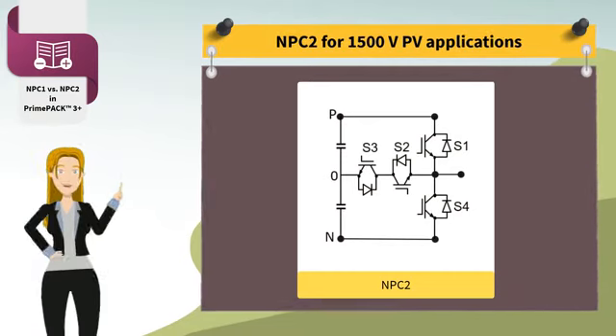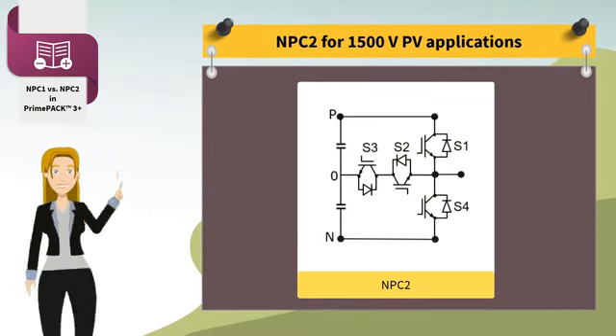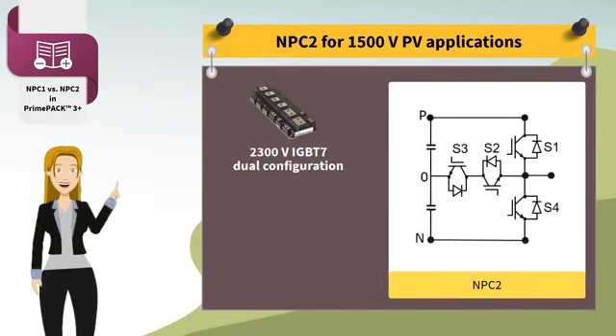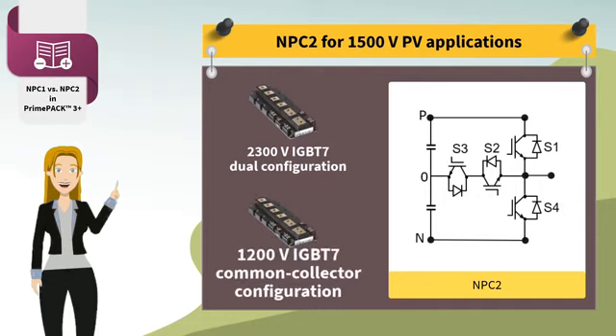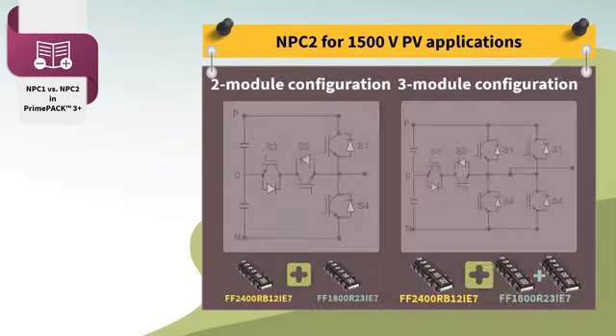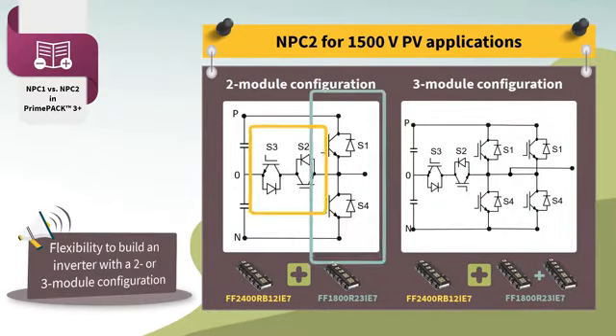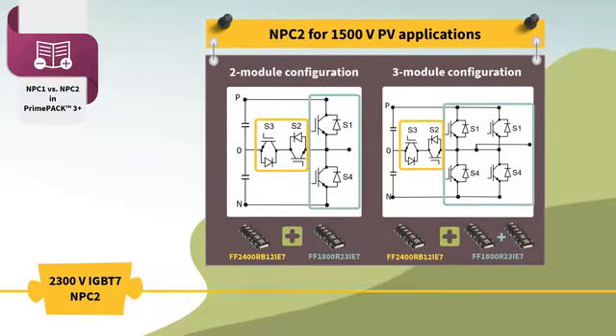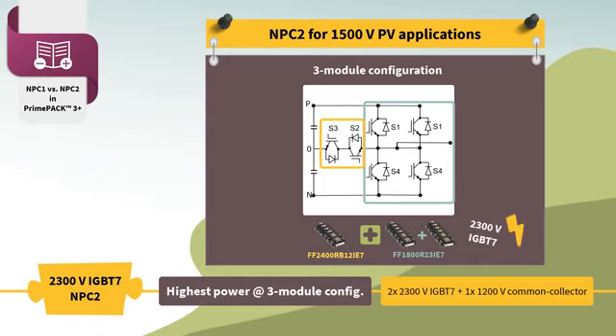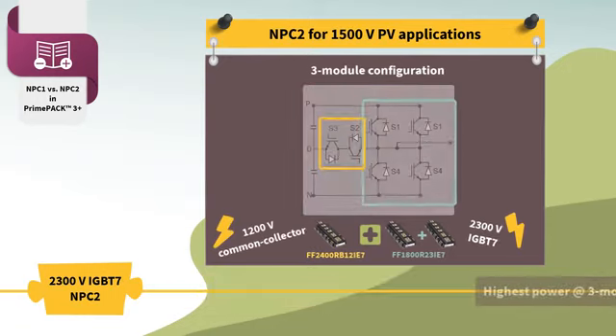To address NPC2 topologies for the 1500V PV applications, Infineon has developed two modules: one with a 2300V IGBT-7 chip in a dual configuration and another with a 1200V IGBT-7 chip in a common collector configuration. This gives you the flexibility to build an inverter with a 2 or 3-module configuration. However, the highest power level can only be achieved in a 3-module configuration, which requires two 2300V IGBT modules and one 1200V common collector module.